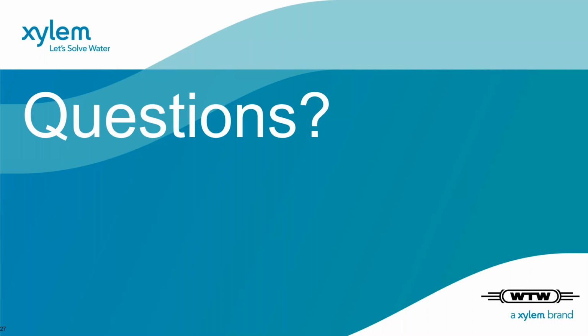Terrific, thank you. There does seem to be a general confusion about the orthophosphate analyzer and the ammonia analyzer. Can one analyzer monitor both? No. It's only for one parameter. Either you take the ammonium analyzer with the Berthelot method, or you take the orthophosphate analyzer with the yellow method. They are 2 different analyzers. Thanks for clarifying that.